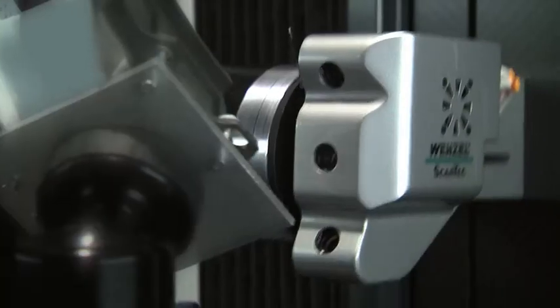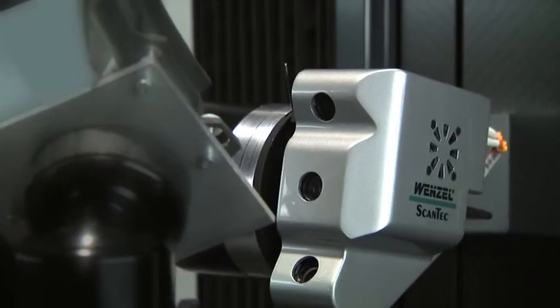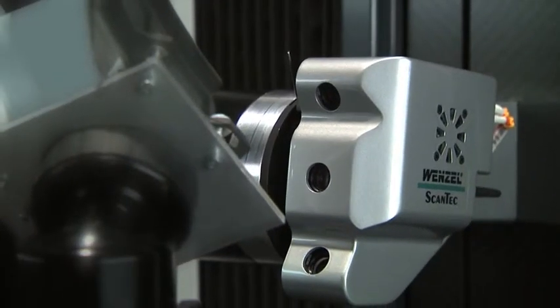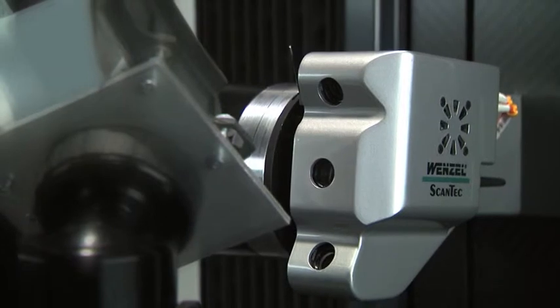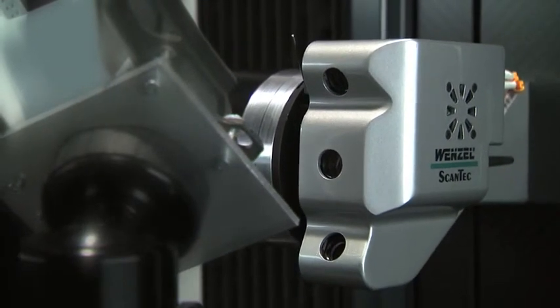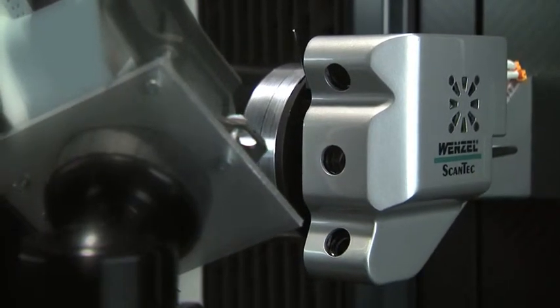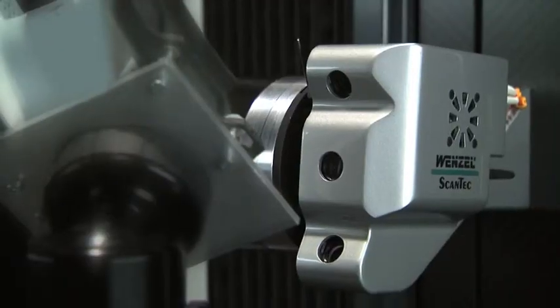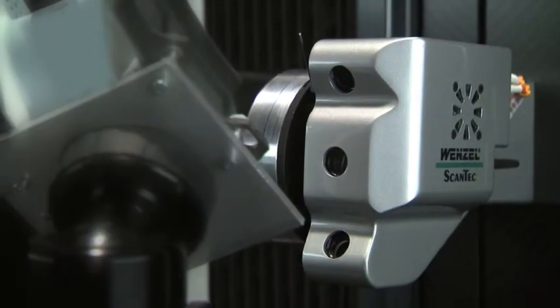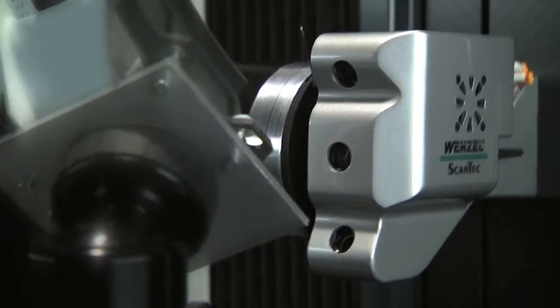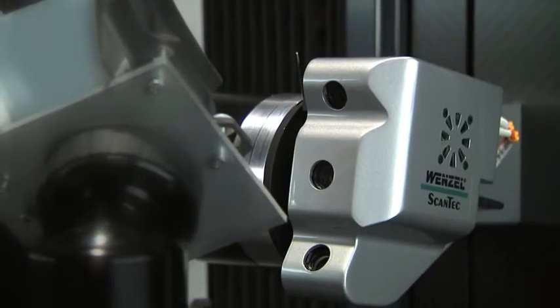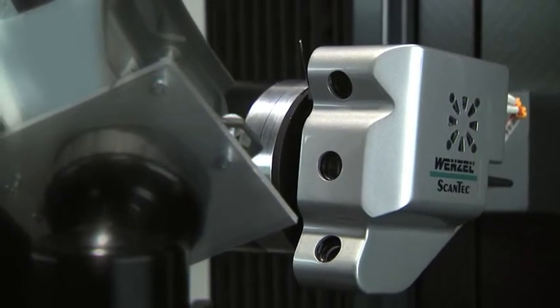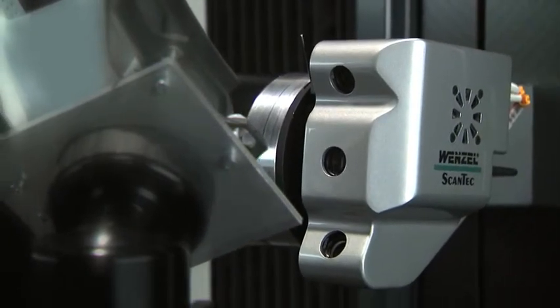The servo controlled CNC swivel wrist with integral high resolution rotary encoder offers a full 180 degree rotation providing complete dexterity when combined with rotary table motion. This allows a full five axis simultaneous motion for measurement of the most complex geometry parts. Maximum scanning speed is up to 400 mm per second across the surface of the part.